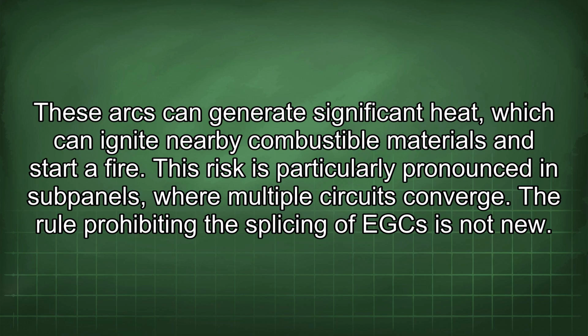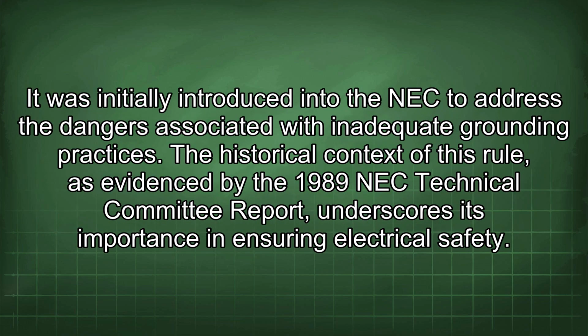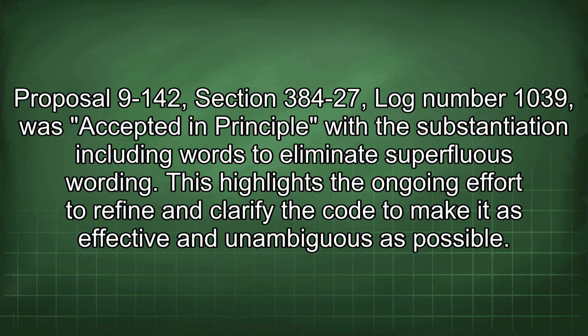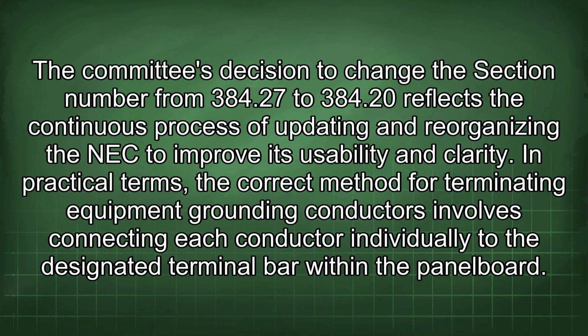The rule prohibiting the splicing of EGC is not new. It was initially introduced into the NEC to address the dangers associated with inadequate grounding practices. The historical context of this rule, as evidenced by the 1989 NEC Technical Committee report, underscores its importance in ensuring electrical safety. Proposal 9-142, Section 384-27, Log Number 1039, was accepted in principle with the substantiation including words to eliminate superfluous wording. This highlights the ongoing effort to refine and clarify the code to make it as effective and unambiguous as possible. The committee's decision to change the section number from 384.27 to 384.20 reflects the continuous process of updating and reorganizing the NEC to improve its usability and clarity.